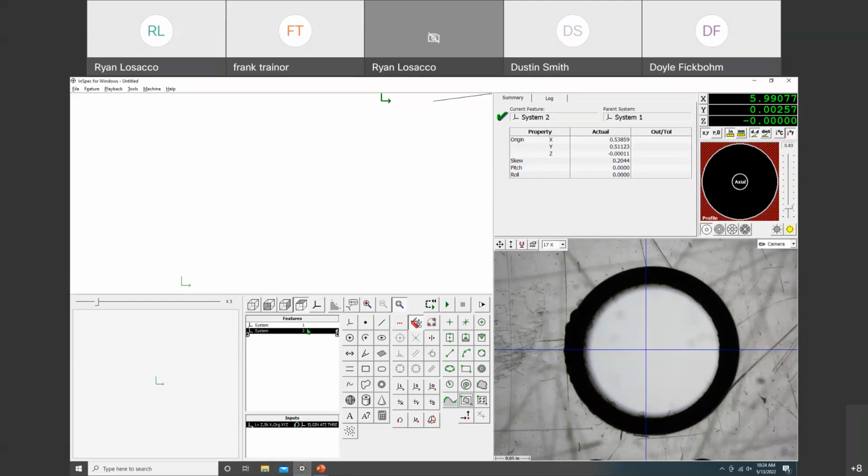If you are having issues after a machine gets calibrated and you're recalling the reference system, give me an email and we can help you enter in the recall stage square system there. So those are some good habits to get into to make your programs last long. If you get new glass, new stage squares, or different fixturing, it's a good habit to get into.